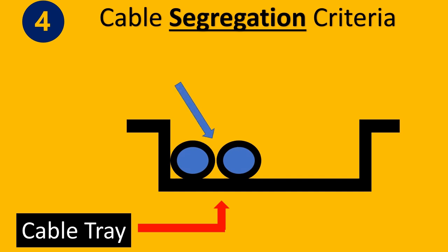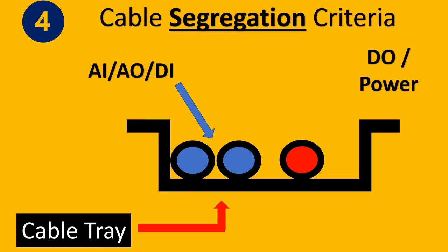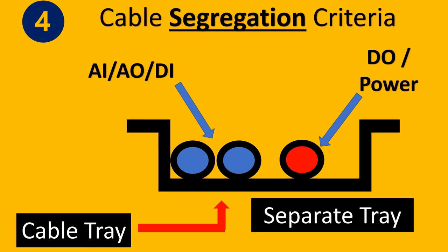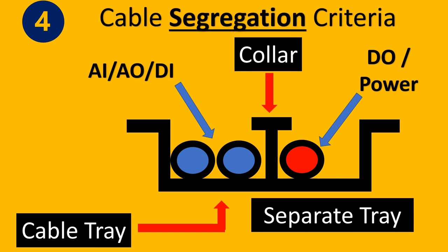Step four is the cable segregation criteria. Imagine your cable tray has AI/AO/DI cables. If a power cable carrying high current is also present, you don't want it to interfere with your analog input or analog output cables. So you either have a separate tray or place something called a collar in between so that interference doesn't occur. This also affects how much space you need and whether you need one cable tray or multiple cable trays.